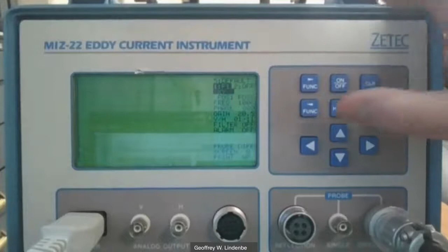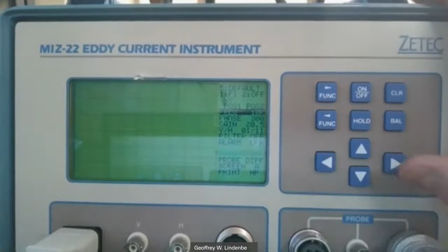I'm going to leave it on the XY plane. For frequency, you can start around 100. If I go up and down, it moves in 10,000 hertz increments. If I go left and right, it multiplies or divides by 10, so use left and right to go quicker, or dial it in precisely, say 120,000 hertz or 120 kilohertz. Phase I'm not going to worry about just yet.